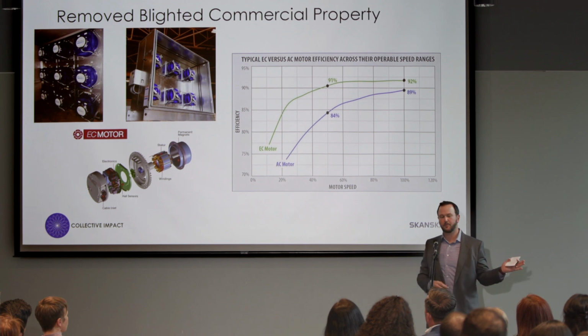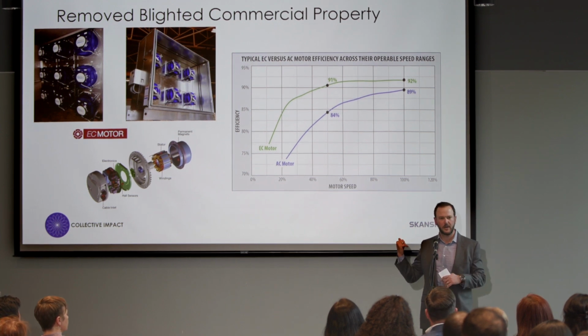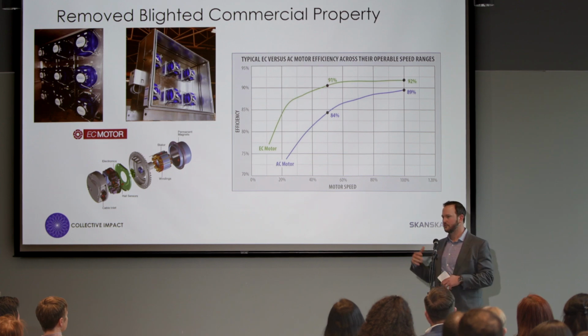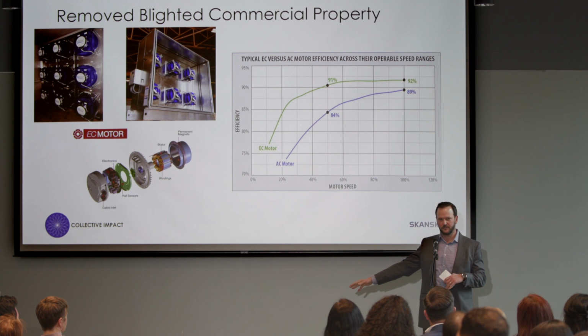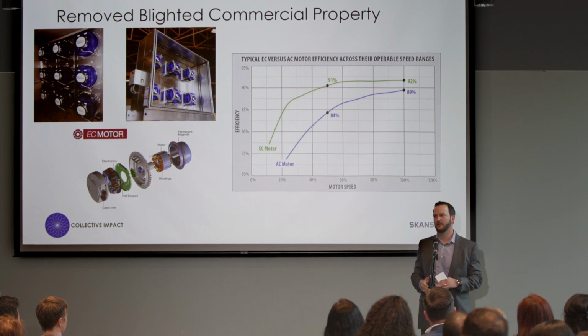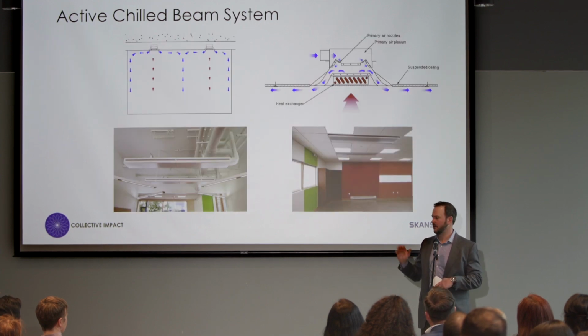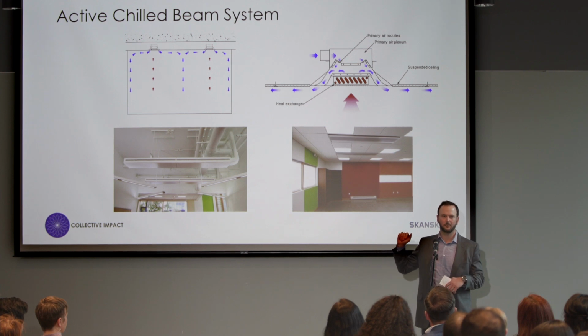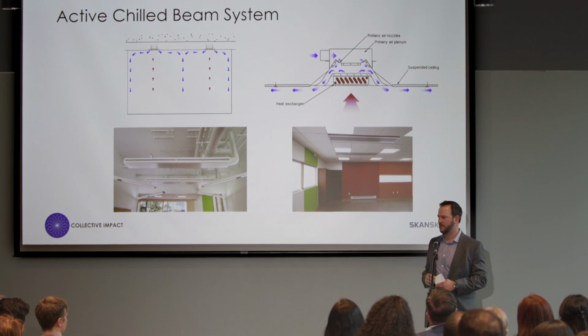On the project at 1550 on the Green, we have these fan arrays totaling about 6.5 brake horsepower, versus a traditional system — even a very, very efficient one like this building would have had — which would have been about 10. So this is fairly new technology being applied to reduce fan energy.